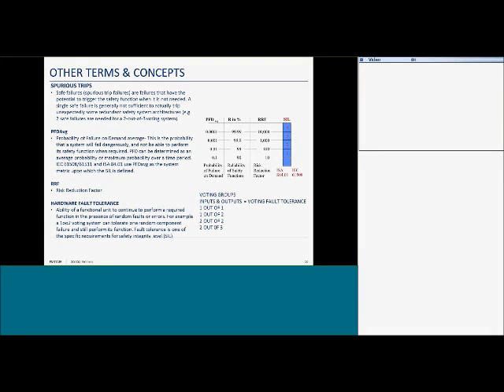So you might see dual solenoids on automated valve packages. That's another way to address hardware fault tolerance. You might see more than one valve, for example, on SIL 3 systems. You're going to see typically 2 valve packages, 2 final elements. By putting in that redundancy and building up the robustness of the design, they improve their risk reduction factor.